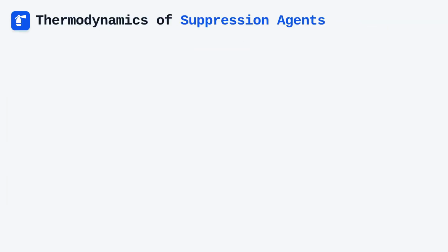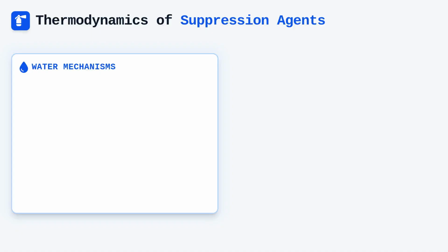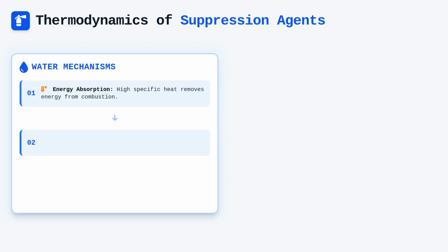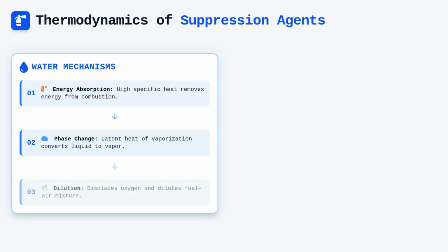The thermodynamics of suppression agents is another pillar we must master to ensure our engineering solutions provide real protection. When we deploy water, we are not simply adding mass to a fire, but utilizing the high specific heat and latent heat of vaporization to remove energy from the combustion process. As water droplets enter a fire plume, they absorb energy to reach saturation temperature and eventually undergo a phase change from liquid to vapor. This process effectively dilutes the fuel-air mixture and displaces oxygen, reducing the reaction rate significantly.